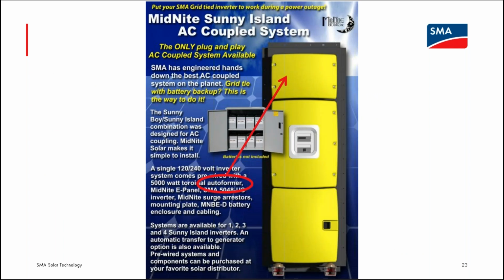They have placed it in a yellow container that has the same curvature and the same color as the Sunny Island. So the device on the top of this panel shown here is an SMA autoformer in MidNite's enclosure. The device below it is the SMA Sunny Island. MidNite Solar makes the back panel, the AC and DC connection panel at the bottom. So there's a DC circuit breaker for the battery isolation, and there are AC breakers for the output of this system. And again, this one system with a single Sunny Island and autoformer will allow up to 6,000 watts, but at 240 volts. It's a fairly tall panel, and the Sunny Island is a fairly heavy device, so definitely it's a nice beefy plate to hold all of this securely.